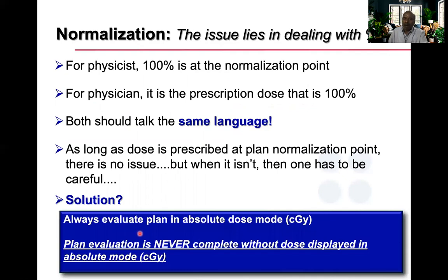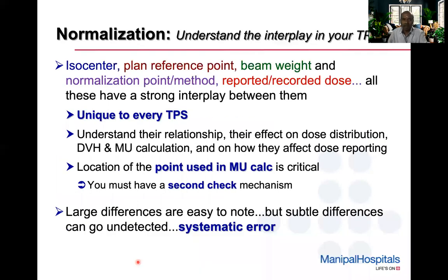The solution is to always evaluate the plan in absolute dose mode — in centigray (cGy). Plan evaluation is never complete without the dose being displayed in absolute dose mode. Understand the interplay in your TPS: the isocenter, plan reference point, beam weight, normalization point method, reported and recorded dose all have a strong interplay, and they are unique to every treatment planning system. Also check the location of the point used in MU calculation — subtle differences can go undetected, resulting in a systematic error.